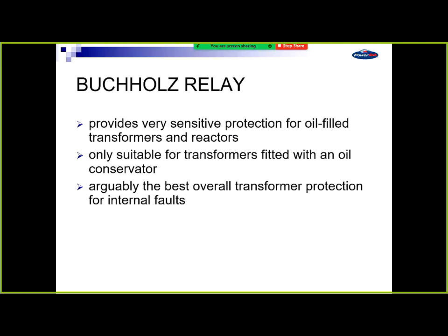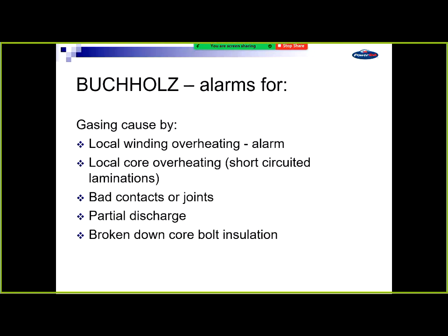With transformers, they've got tap changers, so the current varies from top tap to bottom tap. That arcing could be less than that, could be seen externally just like on a different tap. So you can't pick it up with external protection. So some people say it's the best overall protection for internal faults. You get local winding heating, local core overheating, bad joints, partial discharge, a breakdown in the insulation of the transformer. They're all things that the Buchholz can do.